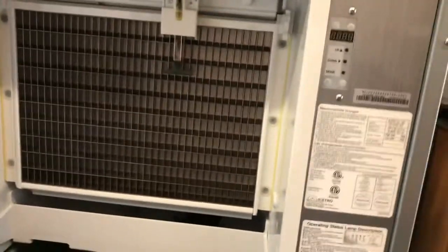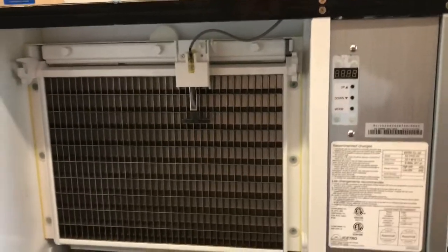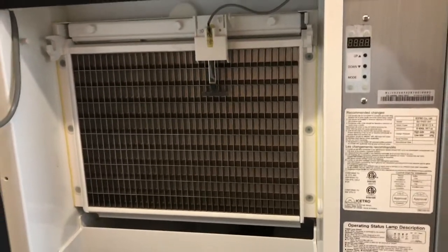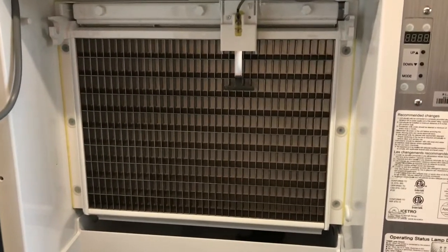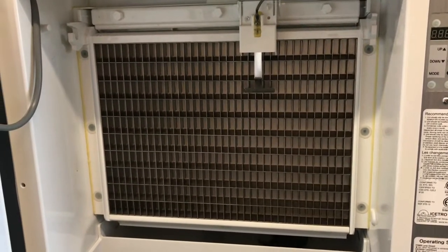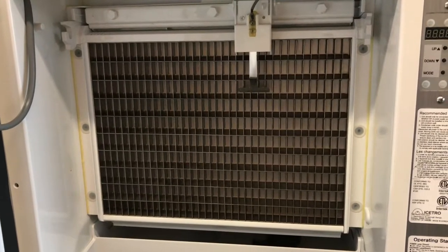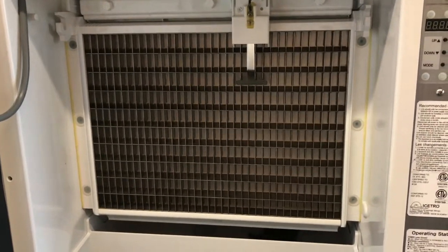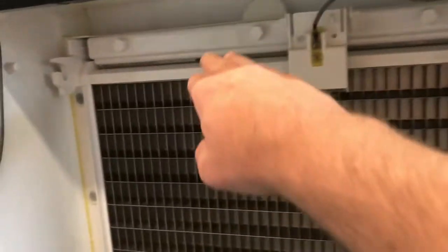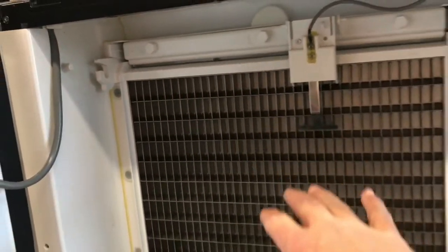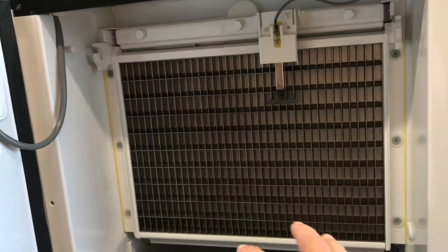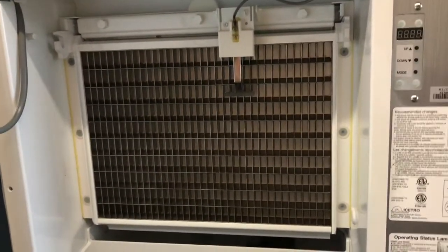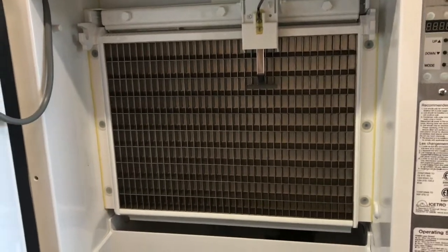So with an ice machine on your evaporator section, you're not moving air over it because you're not trying to cool down the air. You're moving water over it because you're trying to cool that water down, remove the heat out of that water, and cause it to freeze to that plate to make ice cubes. So water comes out of here, flows down the plate. The plate has the refrigerant flowing through it on the back side. It absorbs the heat out of that water and causes it to freeze to that plate.